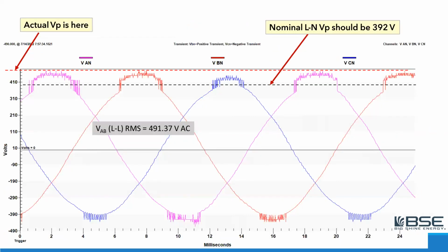Here's another waveform. Now, if I took an electrician's meter and put it on this circuit, I would measure a line-to-line voltage, as you see in this little gray box here, VAB, from phase A to phase B. I'm measuring 491.37 volts. It nominally should be 480. So you might think, oh, it's a little elevated, but that's not a big deal. Percentage-wise, it's not a big change from the nominal.